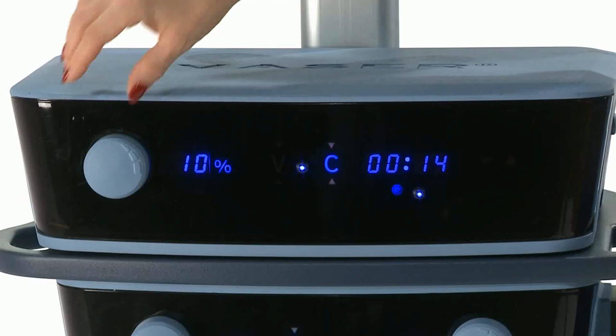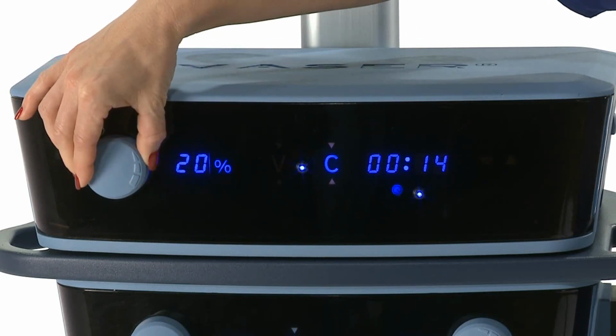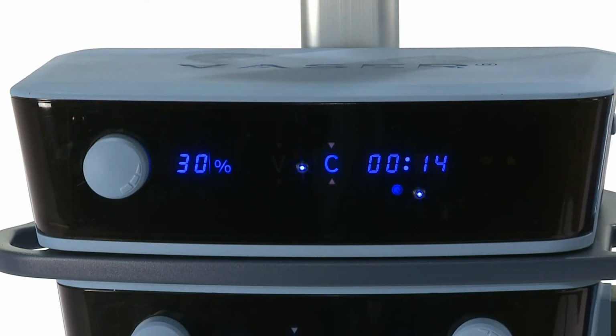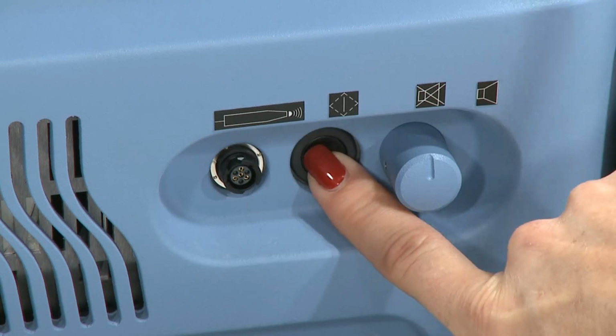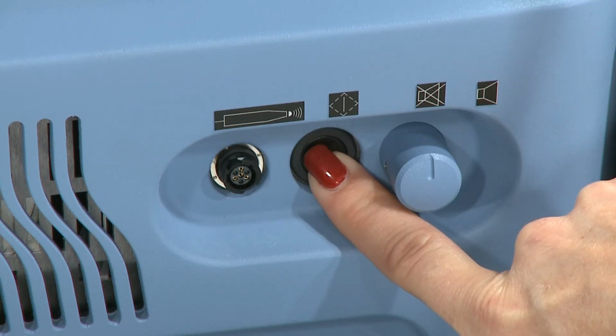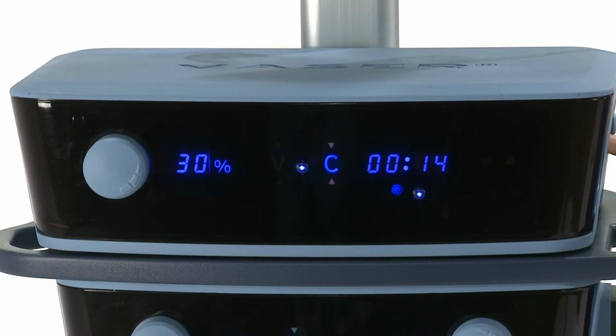Release the Vaser test switch and change the amplitude control to 30%. Again, press and hold the Vaser test switch for at least 5 seconds. This time, you should not see or hear any warning indicators. The Vaser amplifier is operational. If either part of the Vaser test switch fails, call technical support.